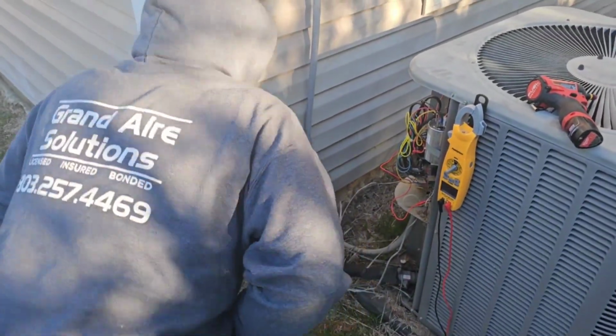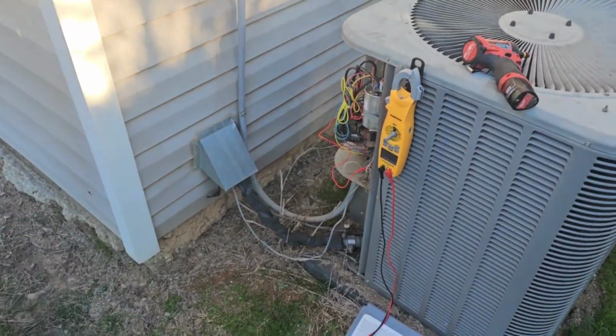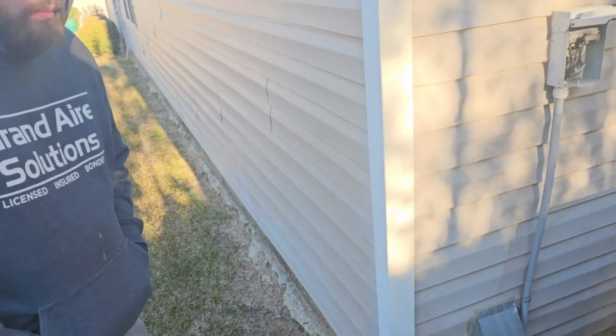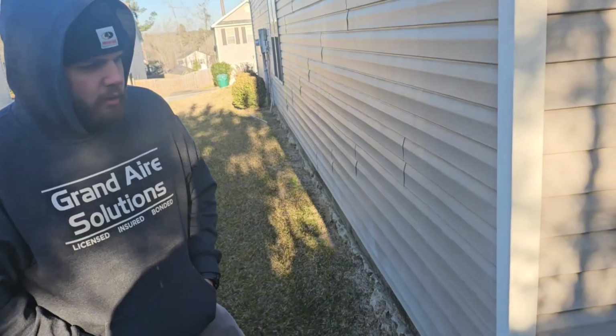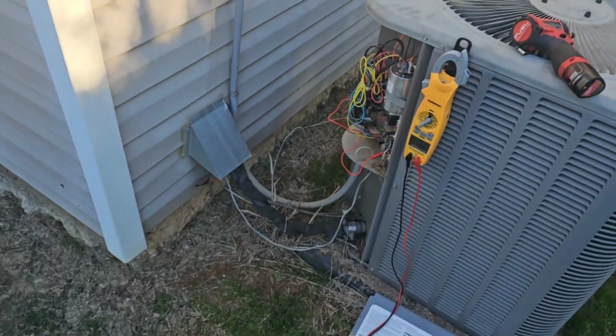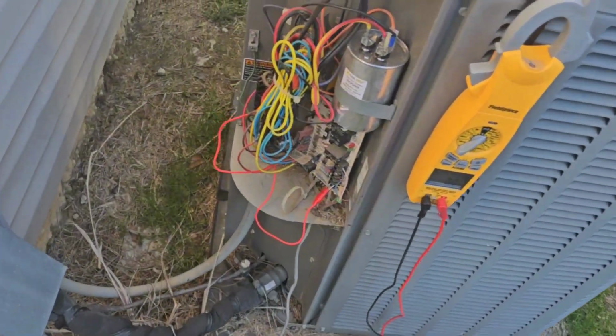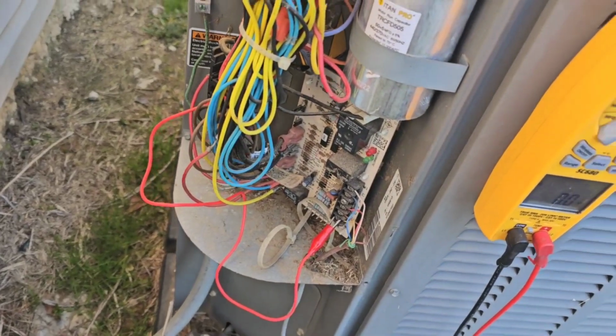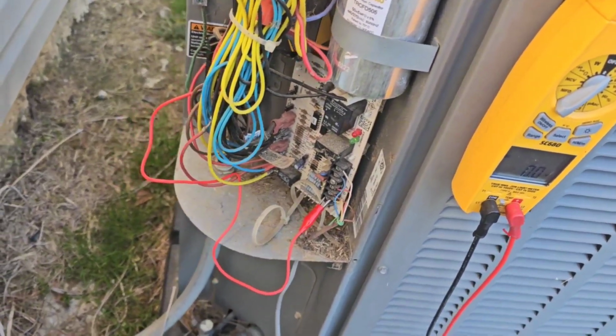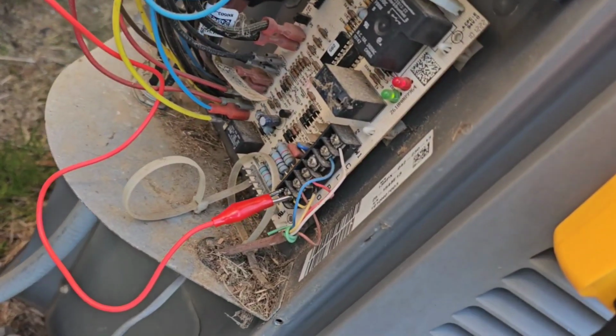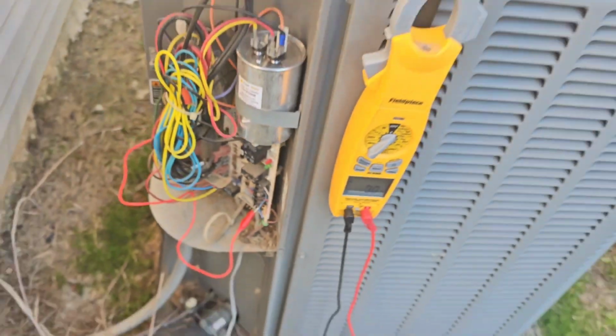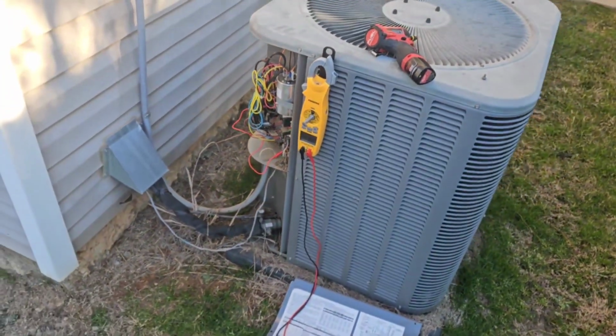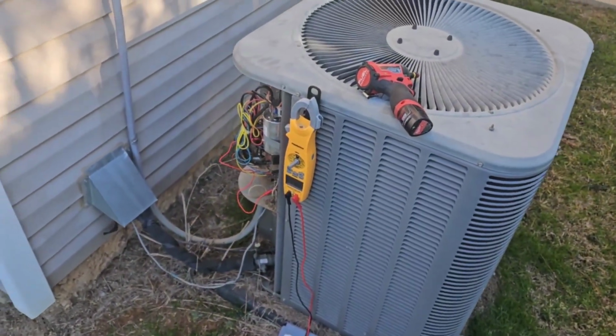So if this test does work, all that's gonna show is that the defrost control board is not sending voltage through one of the terminals to the contactor, which is a very common issue with defrost boards, at least around here, and I don't know why. This unit hasn't really been properly maintained. The coil is dirty. We're gonna have to clean that too, but we're just gonna wait and see what happens.